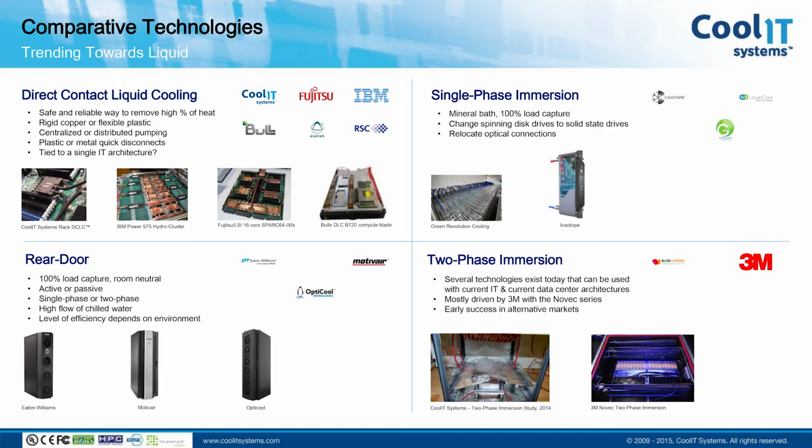So the pumping comes from the heat exchanger. And it's the heat exchanger in this cold plate space, with all the different vendors, that you really see the differences. So we produce a number of different types of heat exchangers. For example, we have heat exchangers for people who can't bring facility water to the aisle, to the rack, to the computer. We use our AHX product. That sort of gives you the race car effect, where it's still exhausting the load out into the data center, but it really allows you to exercise liquid cooling for the performance benefits and the density benefits, just not the efficiency benefit.